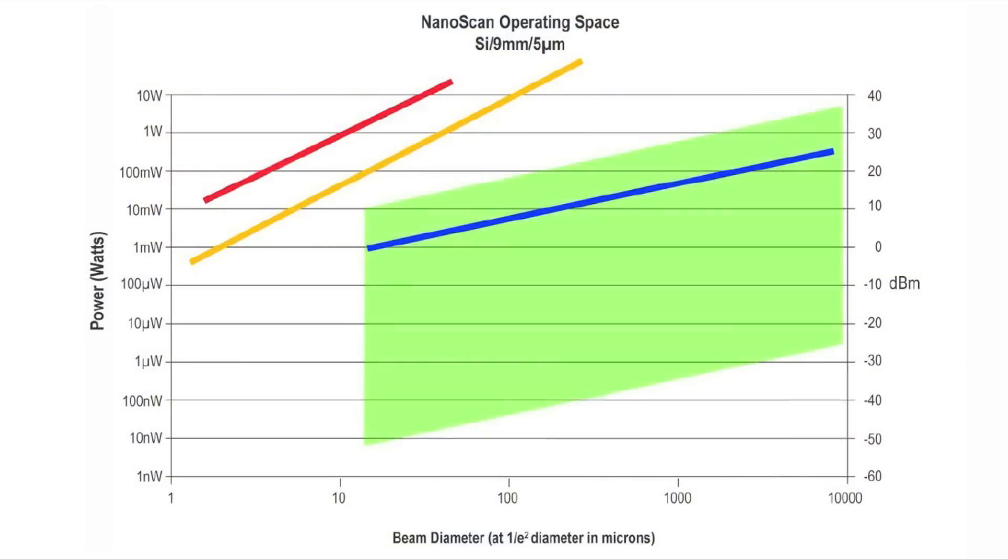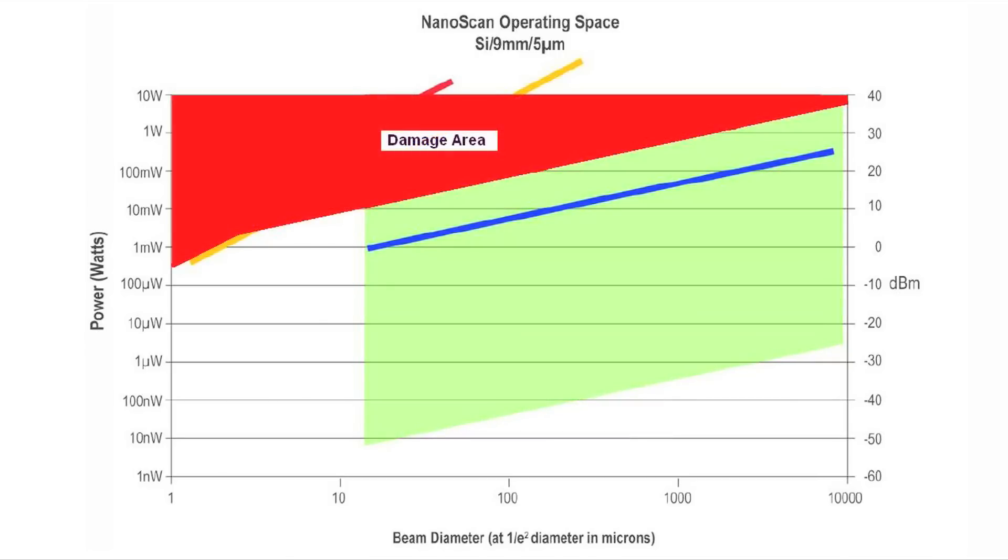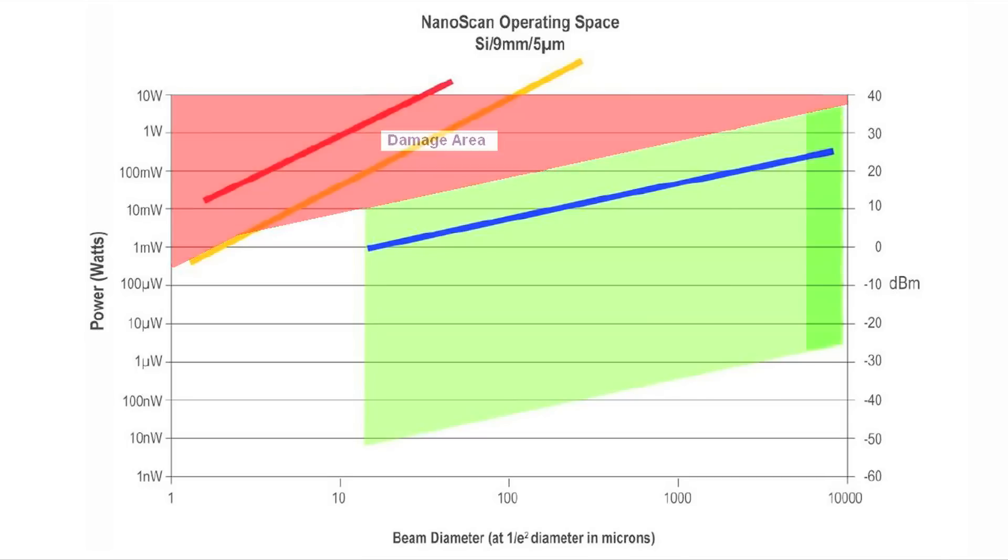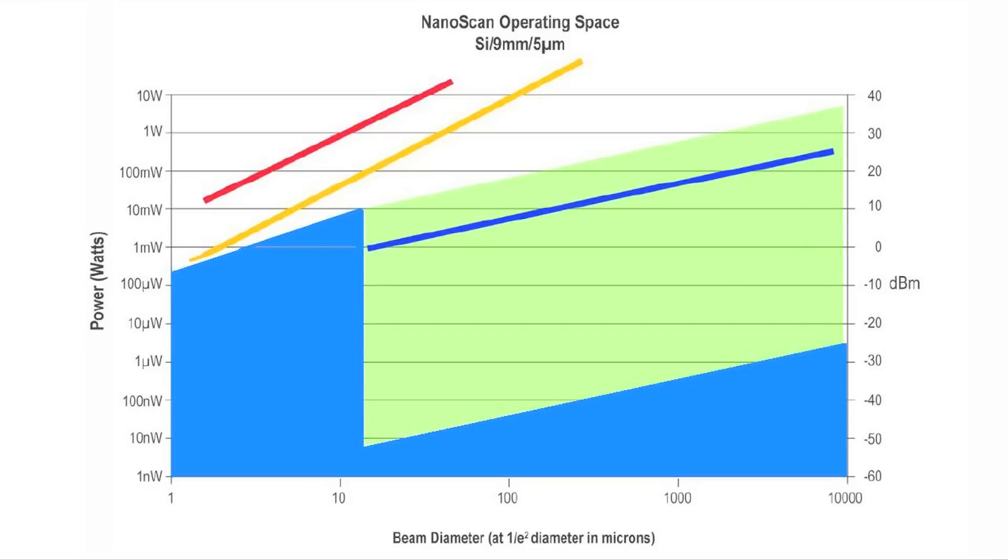Operation outside of the green area means that the nanoscan will not be measuring properly. If you're above the green space, damage can occur. If you operate to the right, you'll see saturation, which results in a wrong measurement. Operation below or to the left of the chart will result in a non-measurement.